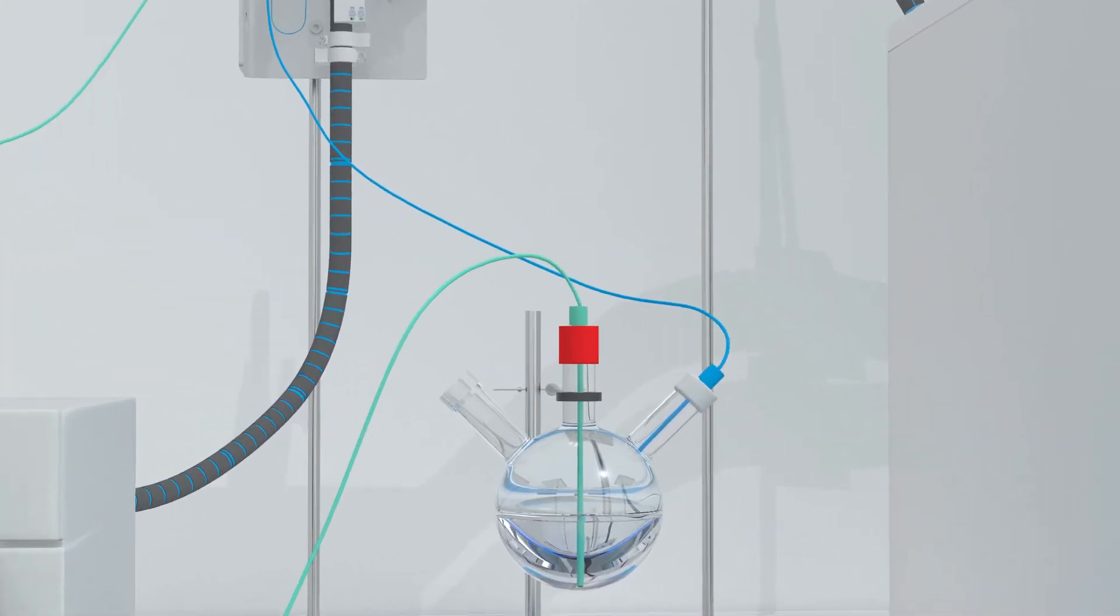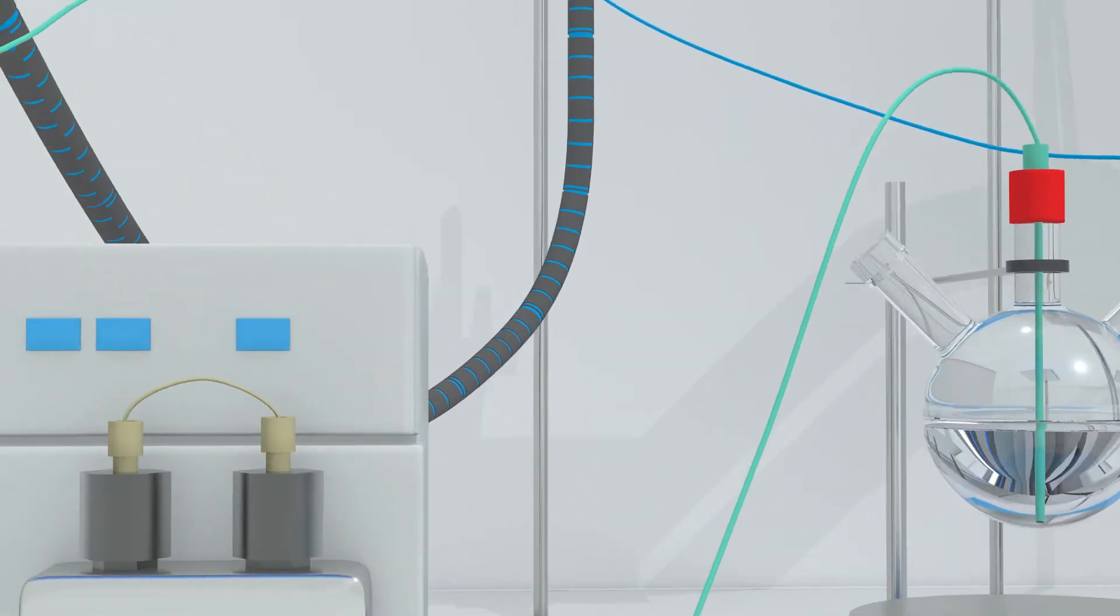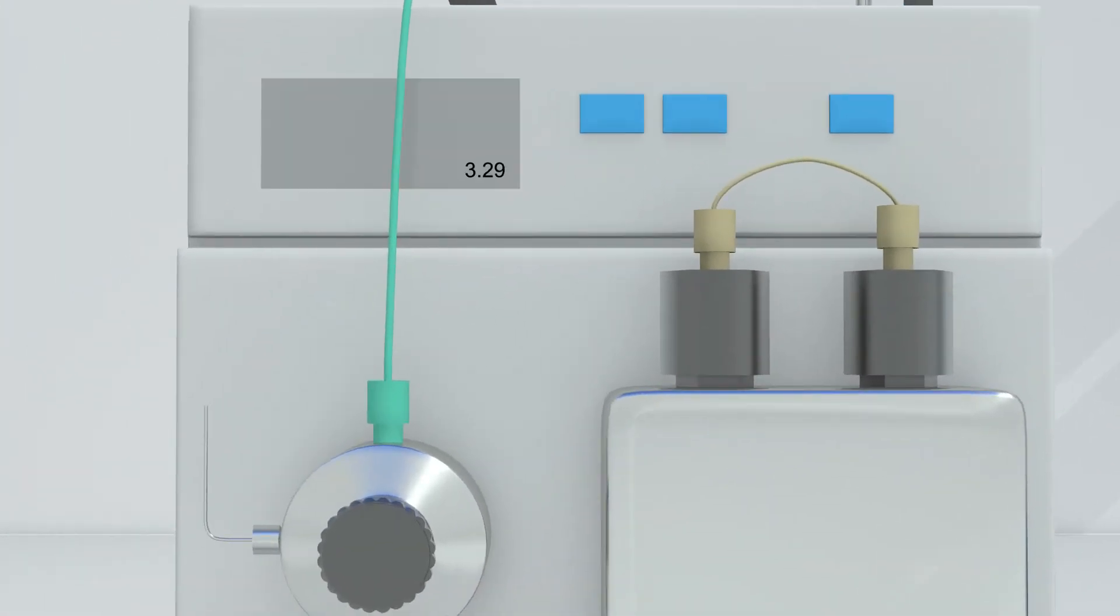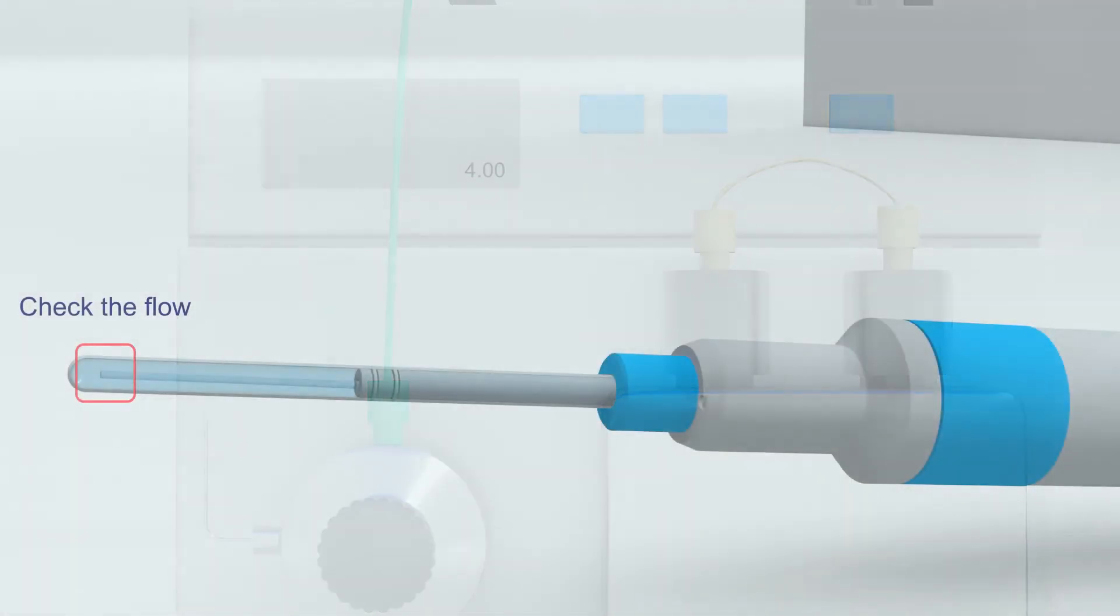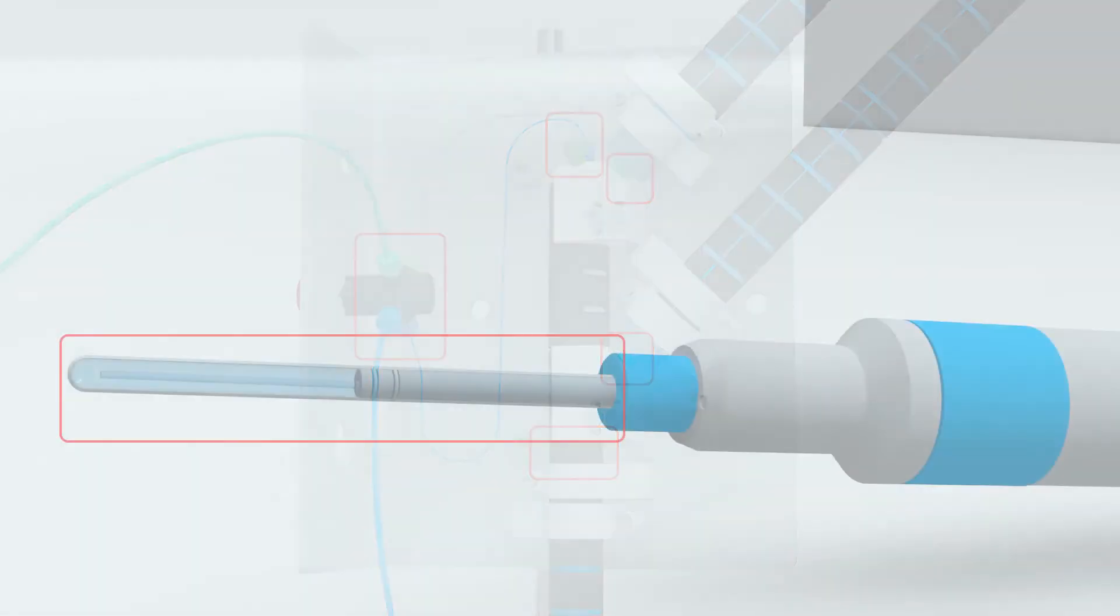Add the desired solvent to the reactor vessel and set the pump to the highest planned flow rate. Switch the pump ON. Check the outlet to see if the flow is correct, and check that there are no leaks from the flow tube assembly, paying particular attention to the connection points.